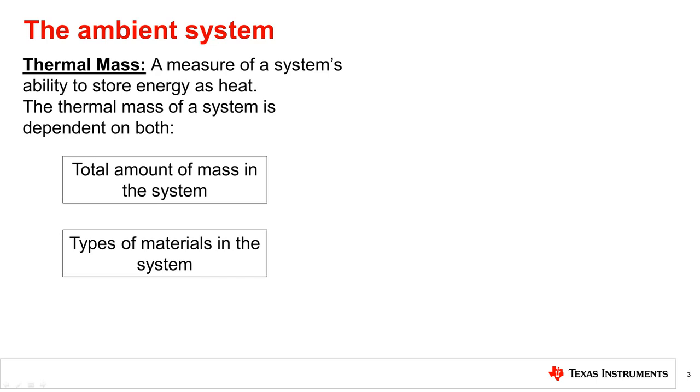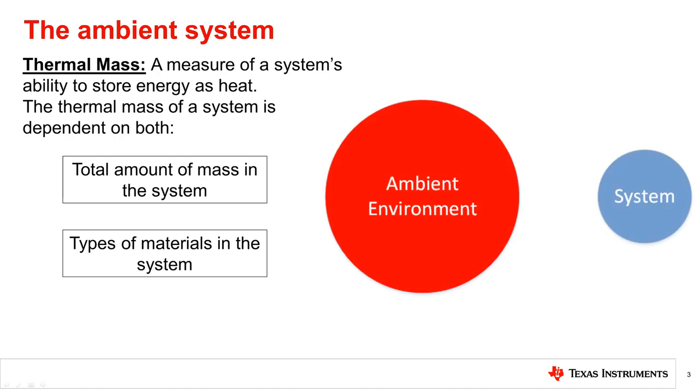To better understand ambient temperature measurements, we need to understand the thermal characteristics of the ambient system and their relationship to each other. The most important of these is the concept of thermal mass, which is the ability of a system to store energy as heat. This depends on both the amount of mass and types of material in the thermal system. In most cases, we have an ambient environment that has significantly greater thermal mass than the system we are using to monitor it.